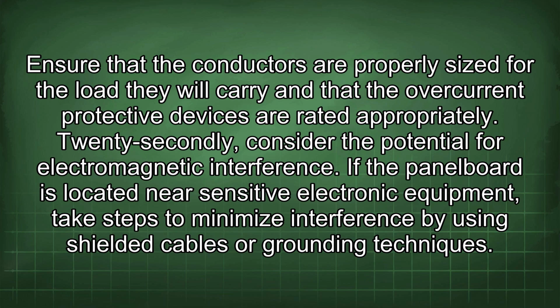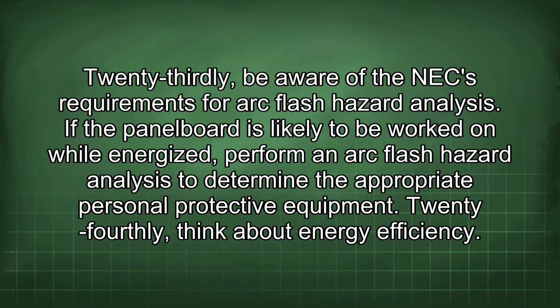If the panel board is located near sensitive electronic equipment, take steps to minimize interference by using shielded cables or grounding techniques. 23rdly, be aware of the NEC requirements for arc flash hazard analysis. If the panel board is likely to be worked on while energized, perform an arc flash hazard analysis to determine the appropriate personal protective equipment.